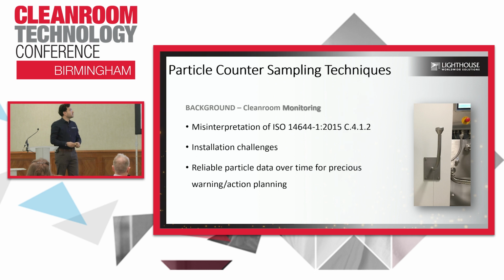So there is ISO 14644-1 Annex C. That was one important section which says that, okay, typically 1 meter tubing length is okay. So don't exceed this. But in most field applications, people pretend to use the same definition for monitoring system design. And everybody says, oh, we designed it for 2 meters. We designed it for 1.5 meters. How are we going to shorten it? Because there are limitations in our system design, how will we handle this? In fact, -1 is talking about classification only, not monitoring. Monitoring is a completely different application.